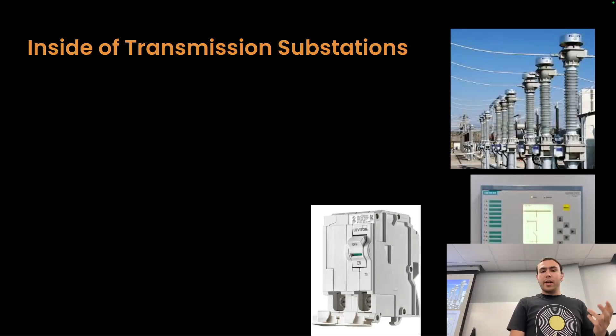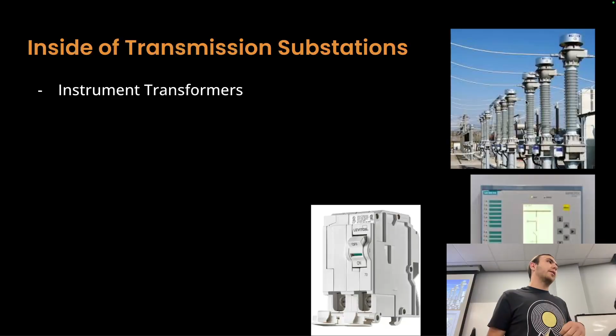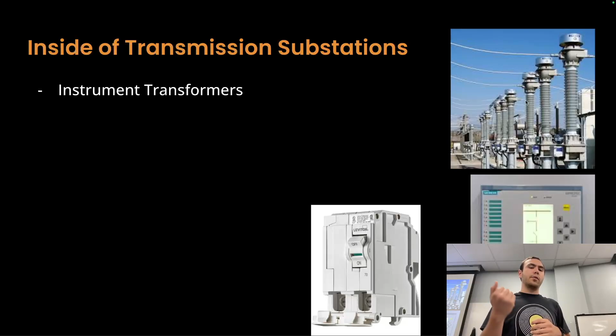Inside some of these transmission stations we have instrument transformers, shown in the image in the top right. These transformers' job isn't to change the voltage of the power itself from low to high or high to low. Instead, they take the voltage or reading from the line and convert it into a sensor-readable amount, since transmission-level voltages are very high. This lets instruments sense a much lower, finer-tuned value.